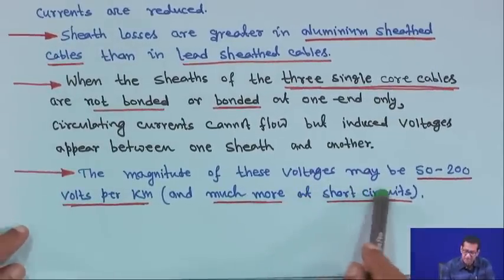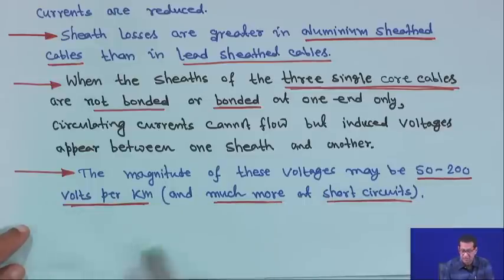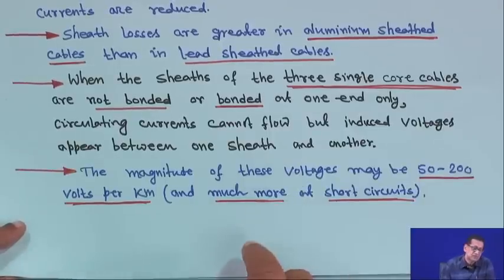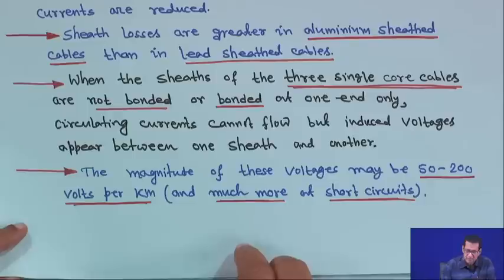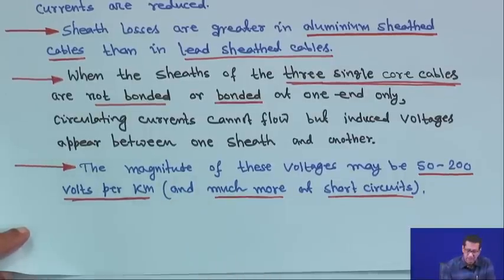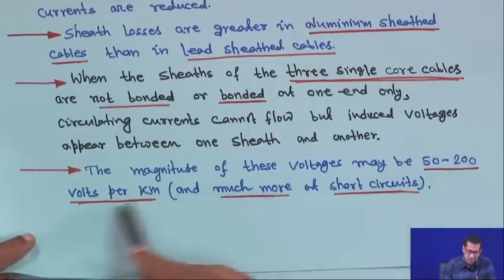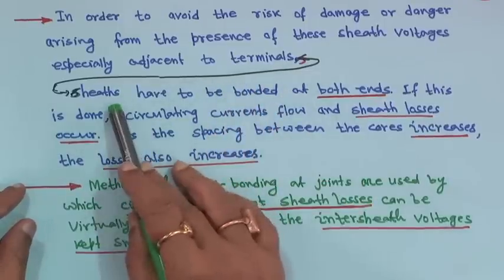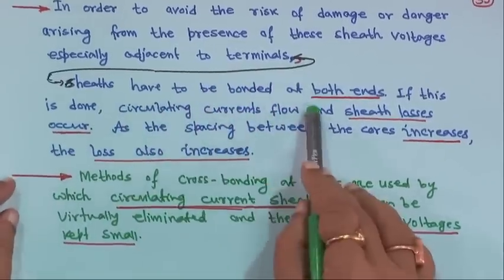The magnitude of this voltage may be 50 to 200 volts per kilometer, and much more at short circuit. If the sheaths are not bonded or bonded at one side only, circulating current cannot flow, but voltage will be induced in this range of 50 to 200 volts per kilometer, and much higher at short circuit. In order to avoid risk of damage arising from sheath voltages, especially adjacent to terminals, sheaths have to be bonded at both ends.